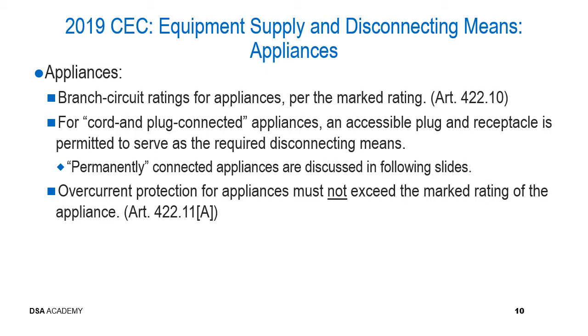On the flip side of the coin, permanently connected appliances are discussed in the following slides, so we'll get to that. Overcurrent protection for appliances obviously must not exceed the marked rating of the appliance. This is obvious, it's understood. However, it is important to state because, again, this is going to be reviewed by the project inspector, and you're going to verify that the disconnecting means or the overcurrent protection device for the appliance matches what the plans say, and that will match what the appliance is.